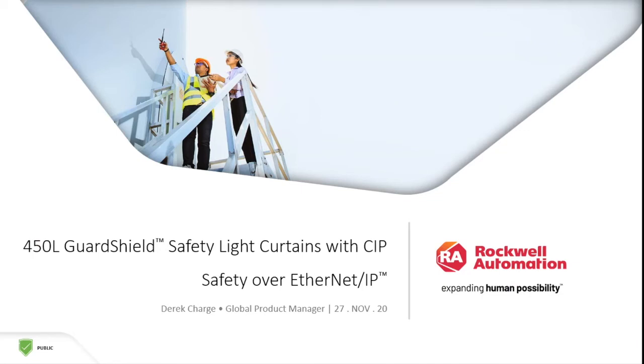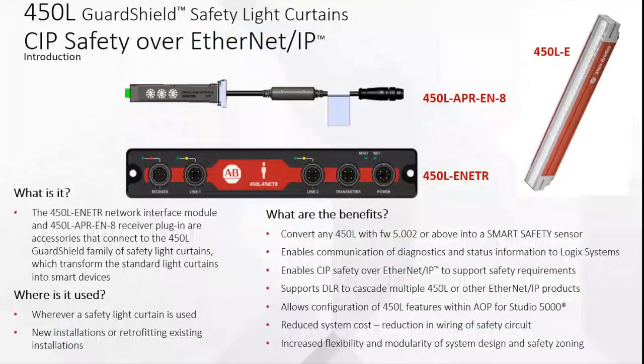Now here's the newest one — the 450L Guard Shield safety light curtains with CIP, Safety over EtherNet/IP. The module shown on top is inserted into the light curtain receiver, the 450L-E, where you set your IP address. That in turn connects to the receiver, the 450L-EN-ETR, and your transmitter. The interface module is pretty slim and easy to mount anywhere on the field or on your production line. You run Ethernet right from that module instead of running cables from your light curtains all the way back to the panel.